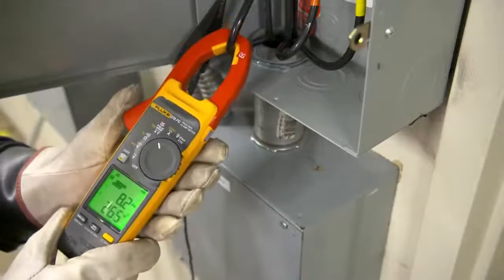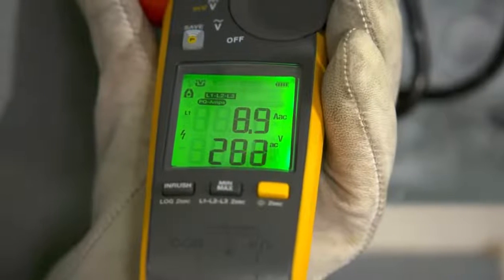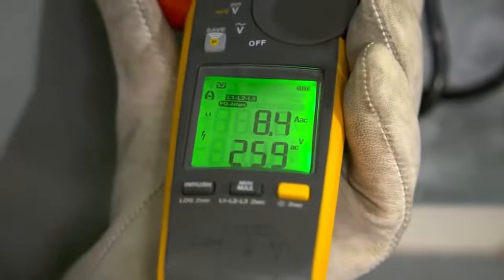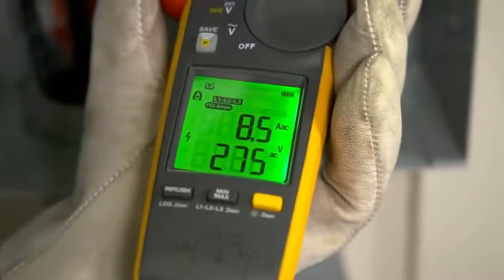While doing so, the clamp senses power problems and shows you if there's a current, voltage, or power factor problem. The meter does this by checking the total harmonic distortion of voltage, current, and power factor. If it exceeds a certain threshold, the annunciator shows up.